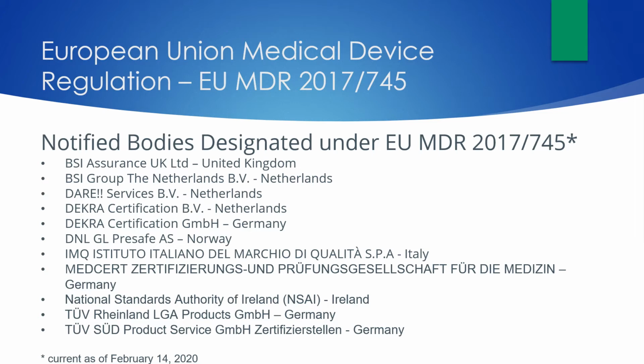Companies are free to choose the notified body they engage with. The notified body must be designated to carry out the conformity assessment procedure for the particular medical device type or types for which the certification is sought. This is the area of major concern for companies as the transition date approaches, because of the small number of notified bodies designated under the new regulation. The number of approved notified bodies above is not foreseen to be enough to handle all the new regulatory approvals needed.